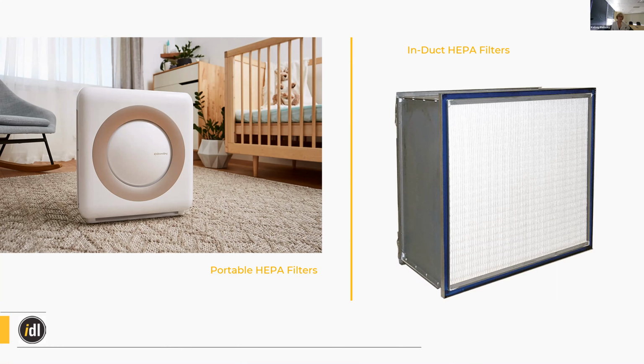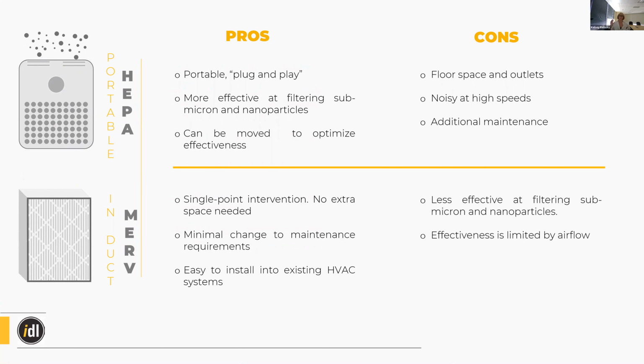So we'll go into it real quick, just because we've seen a lot of those portable HEPA filters in the lobbies of office buildings, or maybe you have one in your home, and then we all have a MERV filter. So I think it's just to lay out the pros and cons of those two commonly used technologies. The MERV filter is great because you probably already have one. It's just a matter of buying one with a higher efficiency. And the portable HEPA filters are also great because they do filter out those submicron and nanoparticles more than the MERV filters will, but they're a higher capital cost up front, and the filters are also a little bit more. But they give you the flexibility to move the filter around where you need it, turn it on when you need it, and such.